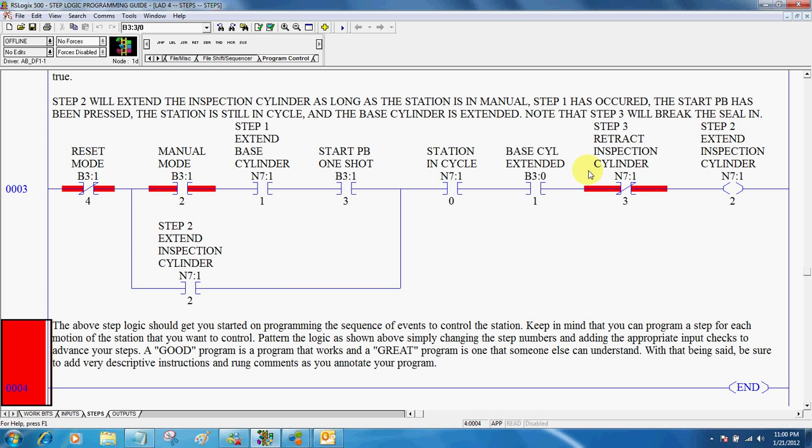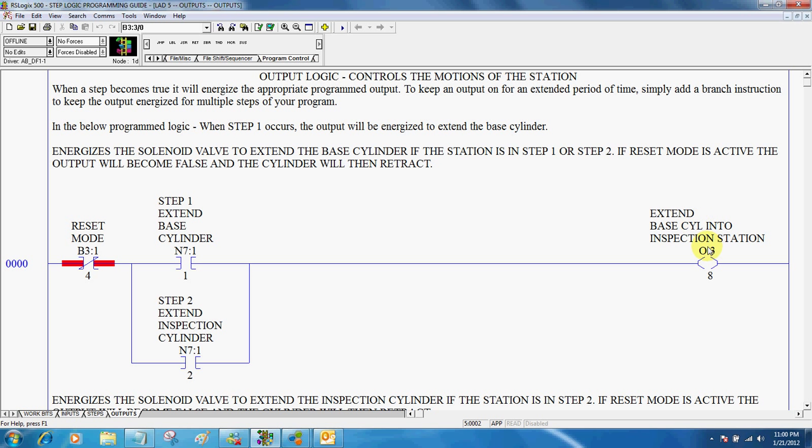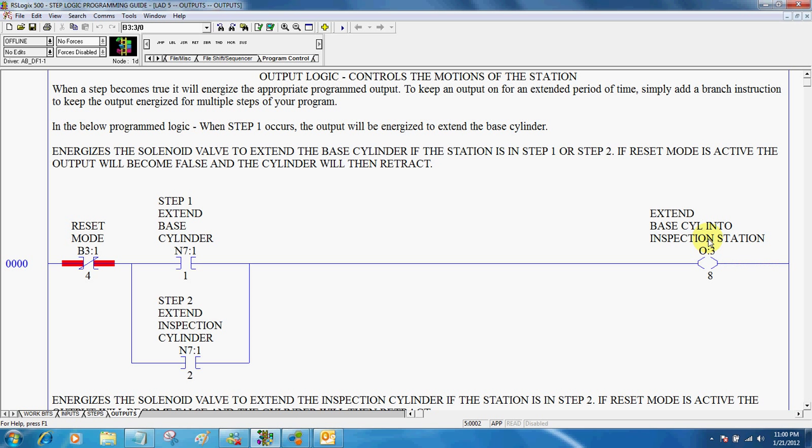After you've written your steps, then you go to your output logic, and your output logic simply just controls your steps. So here, we've got reset mode, we've got step one, we've had step one occur in our logic, and that tells the output to actually come on. Now notice this one is branched, so if it's in step one or step two, it will tell the output to actually come on. So the extend base cylinder in this particular situation would keep the cylinder extended during steps one and two.